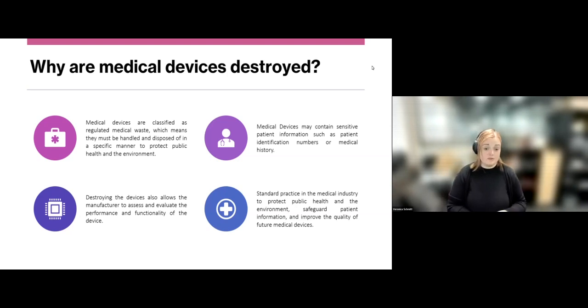Therefore, the devices are destroyed to ensure there's no leakage of data that potentially contravenes privacy laws. The devices are destroyed by the manufacturers after they've assessed and evaluated the performance and functionality—not the actual medical data that's on there. So in terms of whether the manufacturer could give expert testimony on exactly what happened on the device, they can only answer for the fact that performance and functionality were not compromised. But only to an extent, because it doesn't have robust logging—it has medical data logging, but not device logging itself.